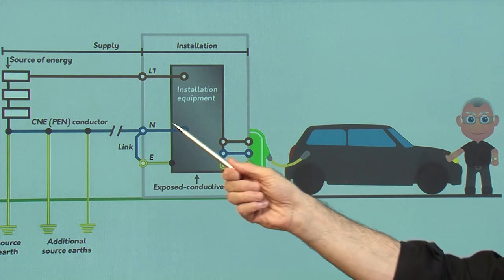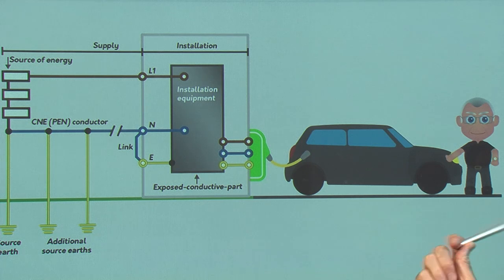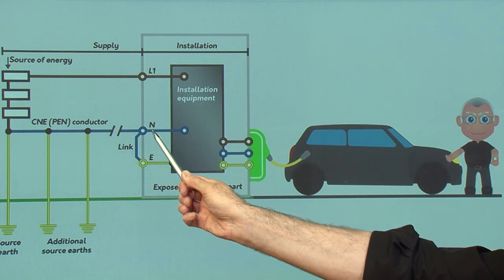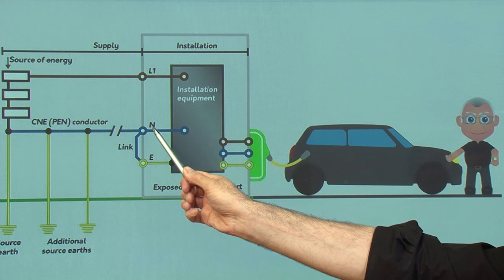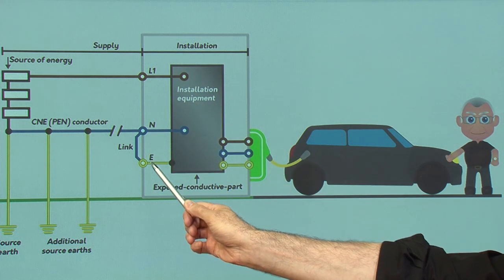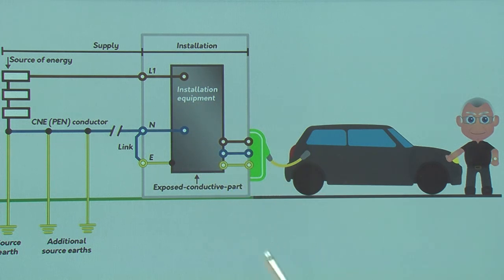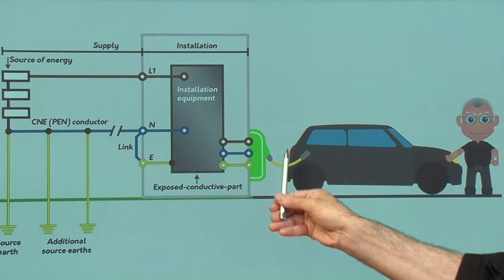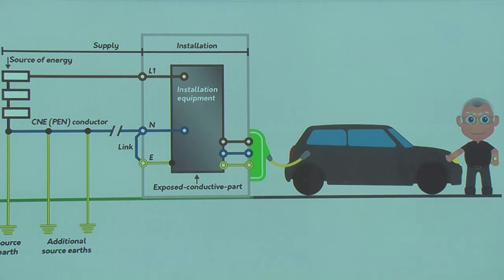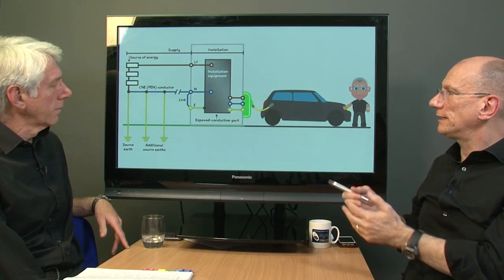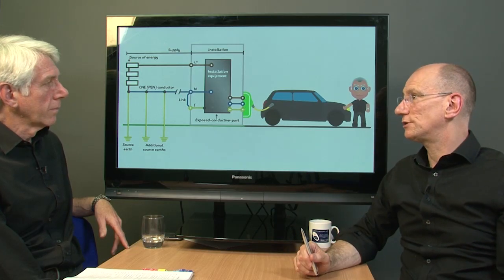So if you end up with a broken neutral, the return path will look for an alternative way to get back. It comes back to the neutral point in the installation, where there's a link to earth. It will try to find an alternative path - if you've got gas pipes or water pipes, it will try to go down there. But in this case, we've exported it out to the vehicle. So if you've got a person in contact with that vehicle and touching earth, this will be raised in potential, and you're at risk of electric shock, which could be fatal.